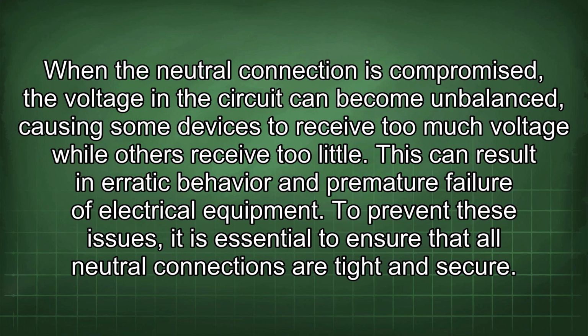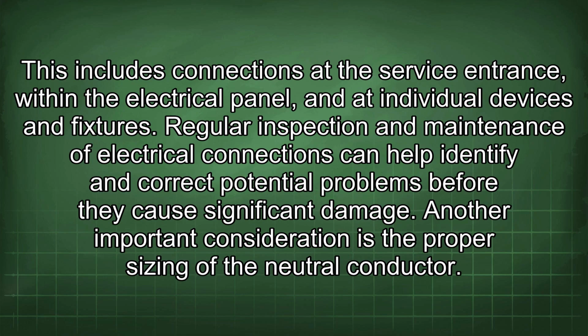To prevent these issues, it is essential to ensure that all neutral connections are tight and secure. This includes connections at the service entrance, within the electrical panel, and at individual devices and fixtures. Regular inspection and maintenance of electrical connections can help identify and correct potential problems before they cause significant damage.